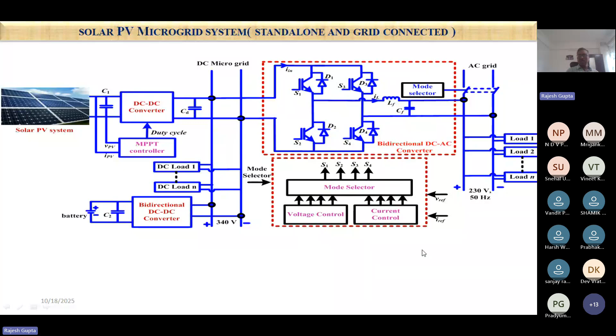This 340 volt DC-DC converter has a control mechanism we implemented using sliding mode control, and through an inverter feeding the main AC grid at 230 volt single phase. So this was a small lab-level microgrid where we created 340 volt DC with renewables and single phase AC, using a grid following inverter for transferring power from the DC microgrid to the grid or vice versa.